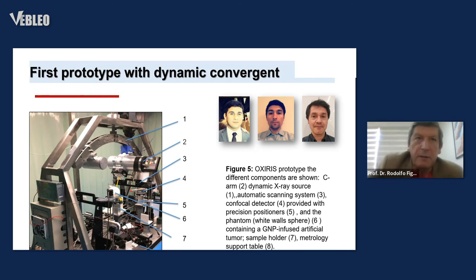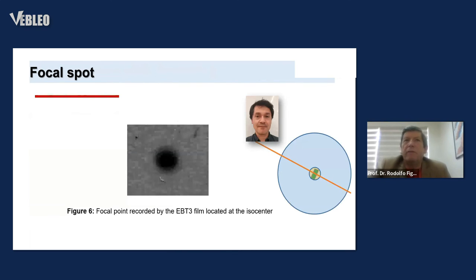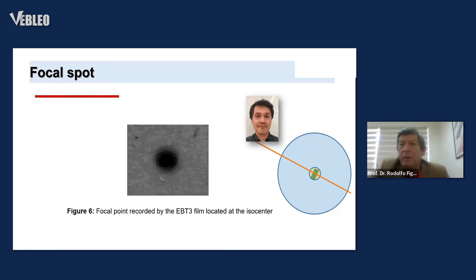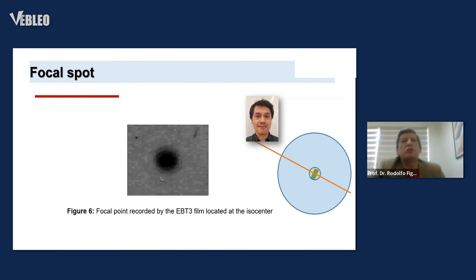The focal spot: the convergence beam is achieved by means of superposition of the concentrating geometrical focal spot, and the beam cross-sectional measurement. A focal spot size lower than two millimeters. Measurements have been performed using EBT3 radiochromic film dosimeter, horizontally positioned. The radio-opaque spot has been approximated by an ellipse. The size is approximately 2x2 millimeters square.